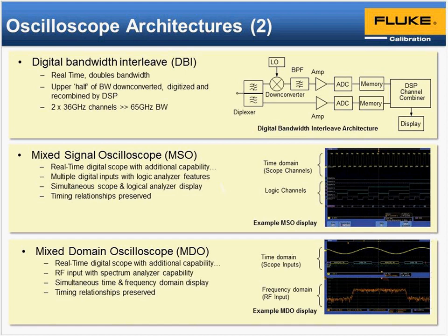And of course, one of the really important things we're interested in calibrating oscilloscopes is because they are very much testing items. They are measuring instruments, not just for a display of a waveform, because they have all of these analysis features, cursor readouts and so on. They are measuring instruments used to measure all sorts of quantities, and therefore we need to be sure that they're giving us the right answer, and we do that by verifying their performance against specifications through the process of calibration.